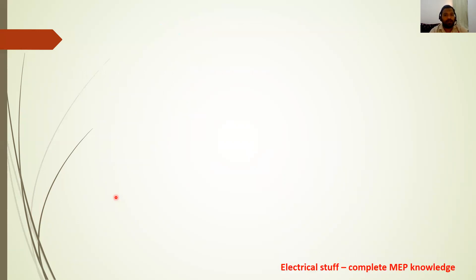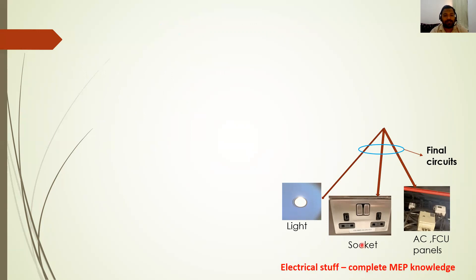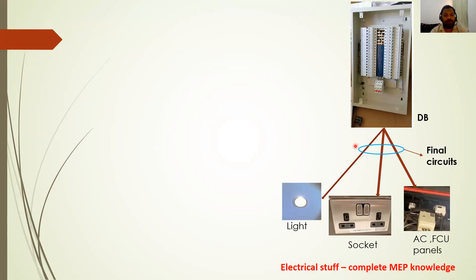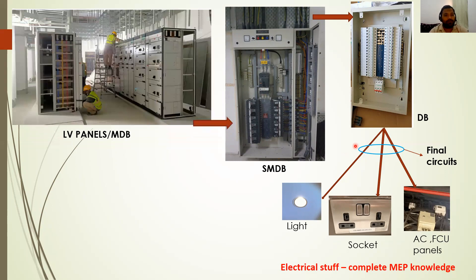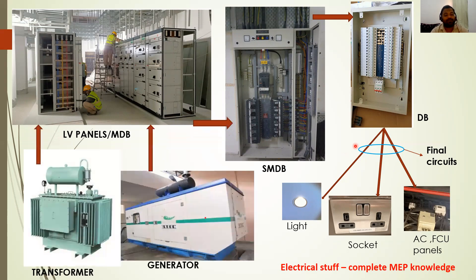Practically, the final loads — lights, power sockets, and AC FCU panels — are called final circuits. These are fed from distribution boards. Distribution boards are fed from sub-main distribution boards, which are fed from LV panels or main distribution panels. Those panels are fed from the transformers or generator. This is how power is distributed in buildings.